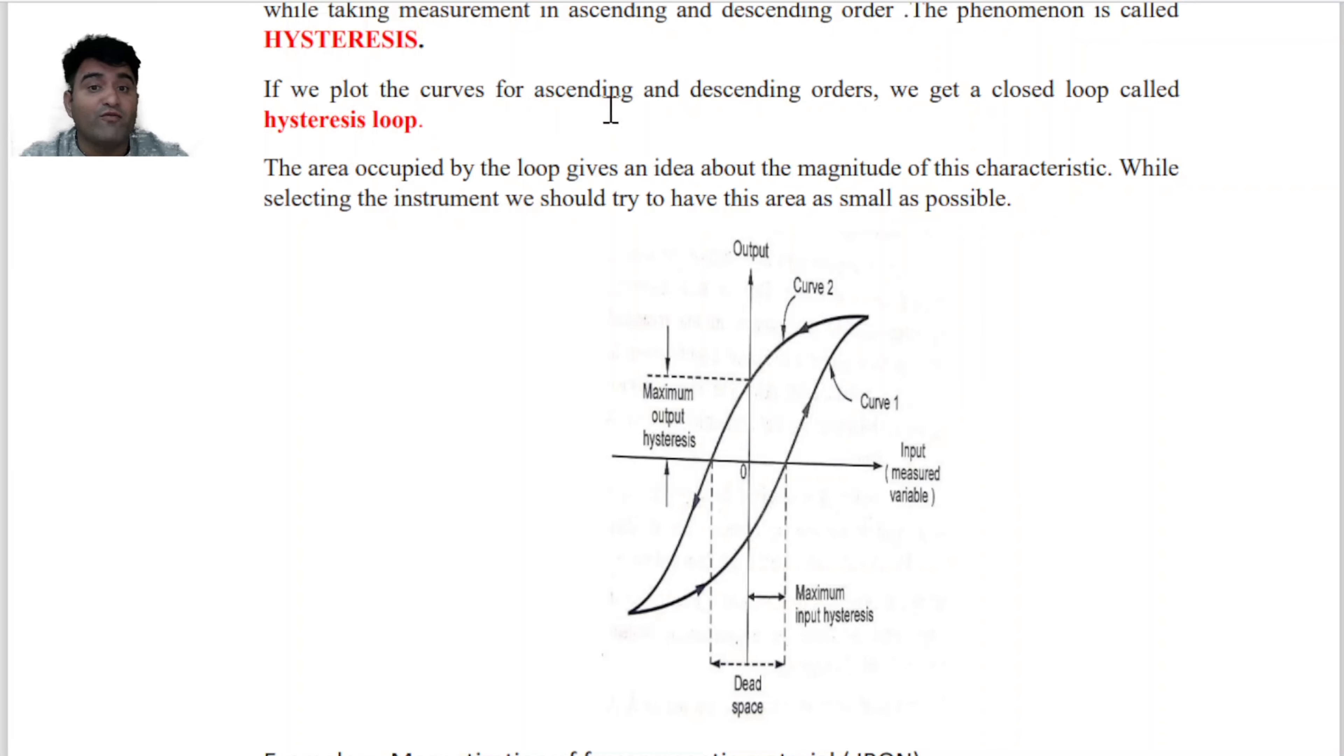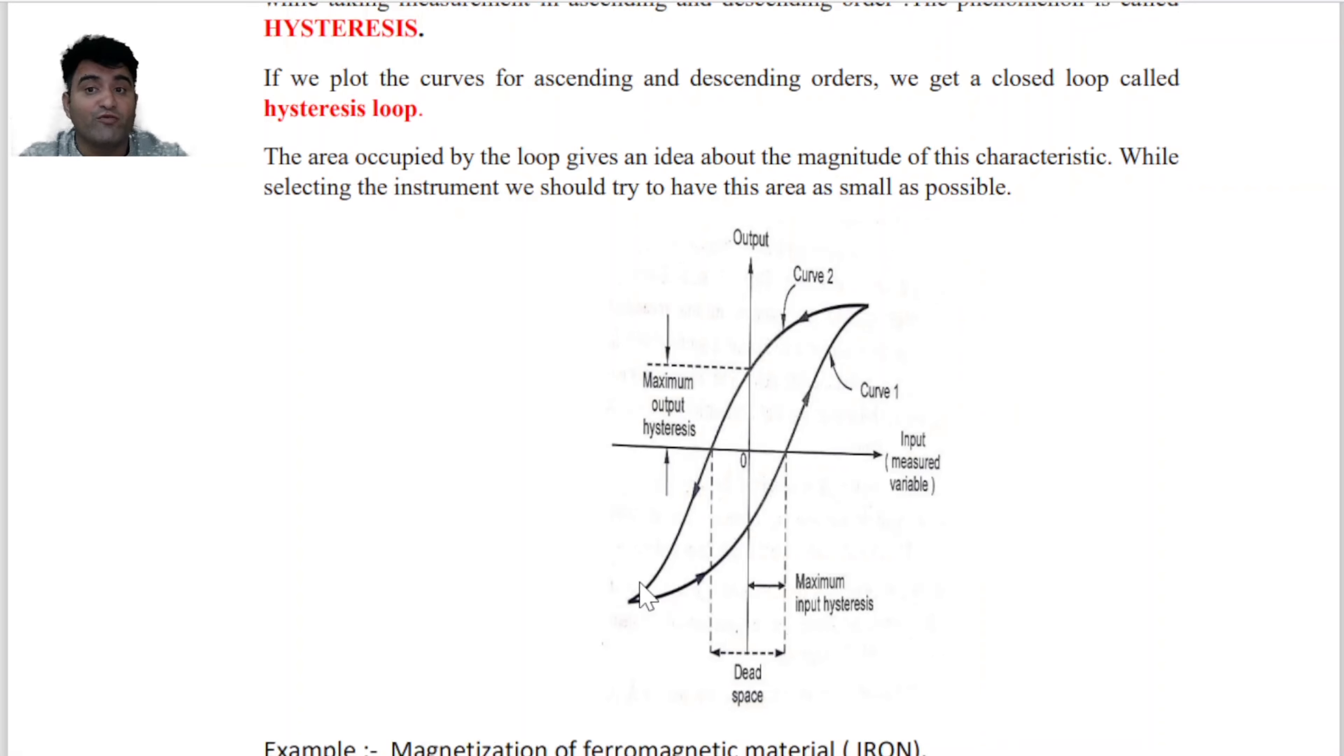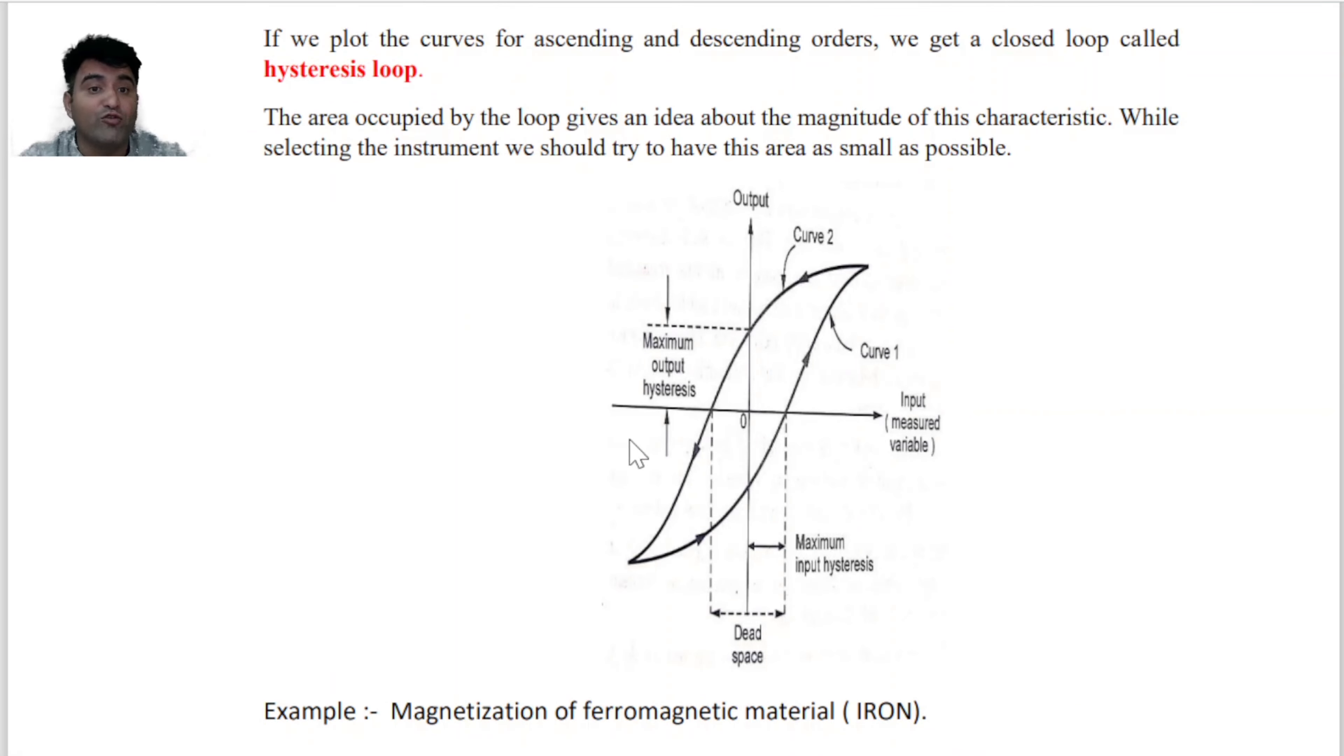If we plot a curve for ascending and descending order, we get a closed loop called hysteresis loop. The area occupied by the loop gives an idea about the magnitude of this characteristic. While selecting the instrument, we should try to have this area as small as possible.